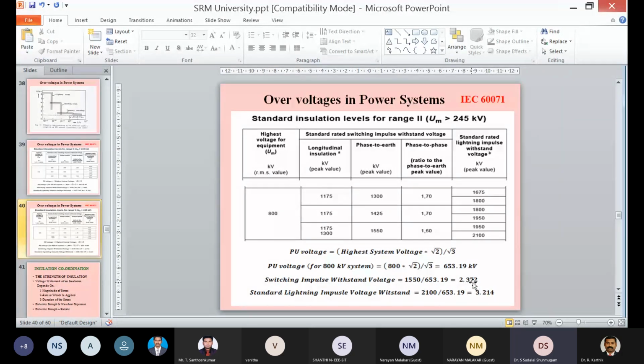So you can see here, after 400 kV, the switching impulse and lightning impulse are coming quite close together. This is a very important key point you should remember, because when it comes to system design and other things, it plays a major role. That is the reason after 400 kV, switching becomes more predominant in the design criteria than lightning, whereas below 400 kV, lightning defines the design criteria more than switching.